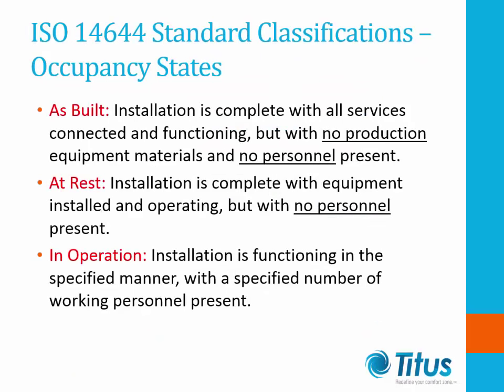When discussing cleanroom air cleanliness class, it is very important to specify the occupancy state. There are three states: as-built, with no production equipment and no personnel; at-rest, with production equipment but no personnel; and in-operation, with installation functioning in a specified manner and with a specified number of working personnel.